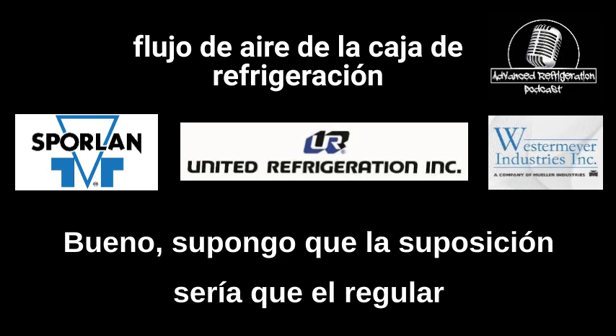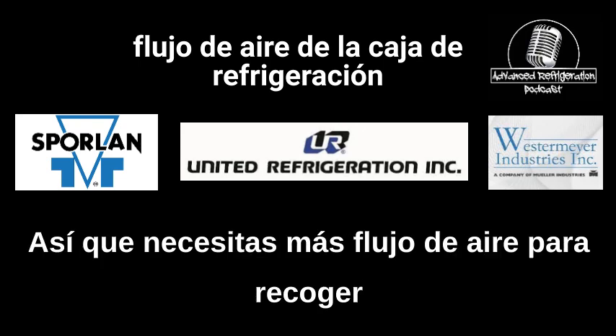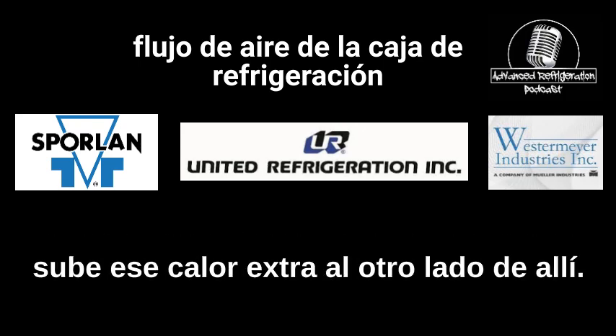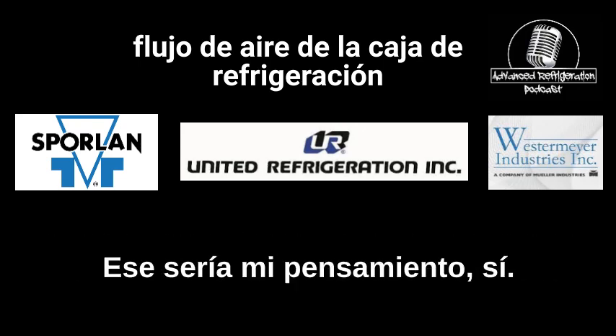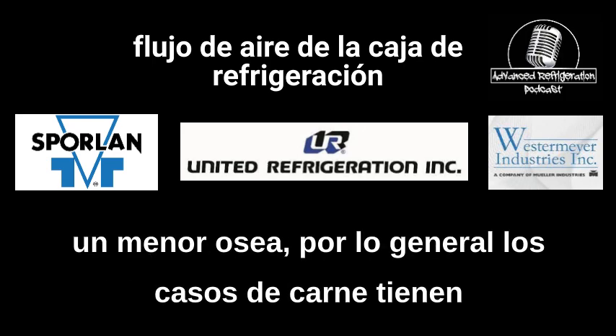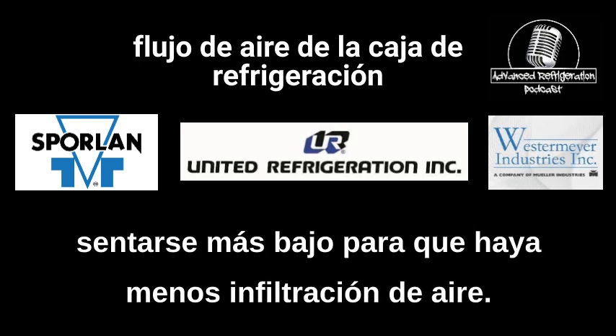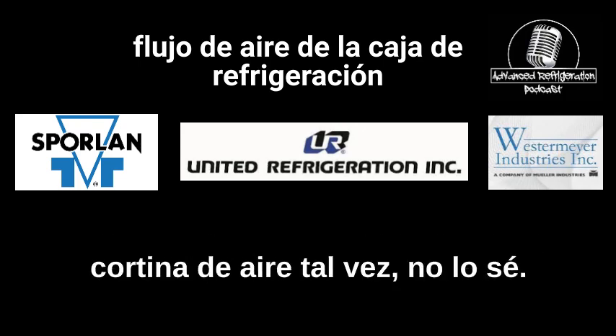Well, I guess the assumption would be that the regular packaged meat is going to hold more heat, right? So you need more airflow to pick up that extra heat across there. That would be my thought. Yeah, and more of an air curtain, because usually the meat cases have the product sitting lower, so there's less air infiltration. So they need more of an air curtain, maybe.